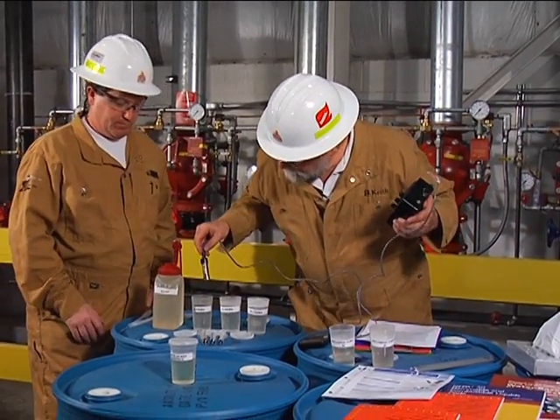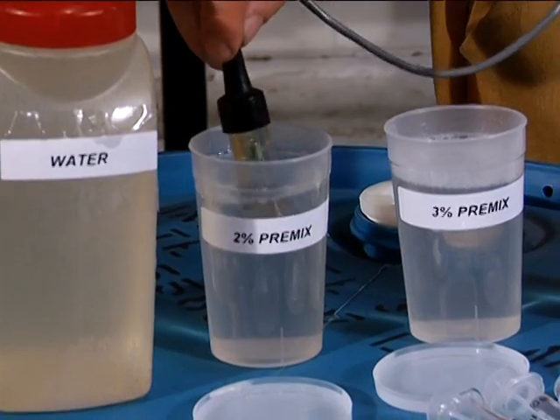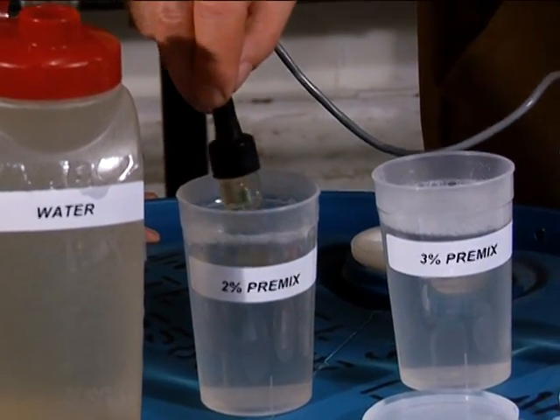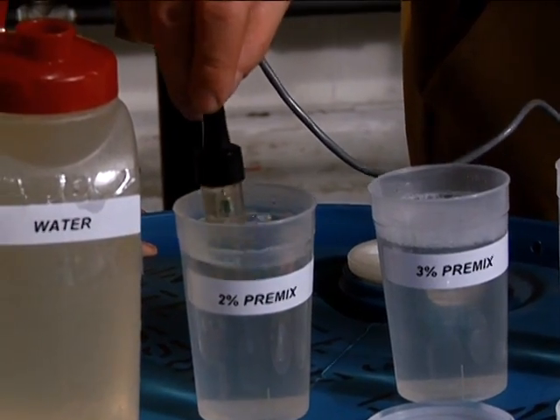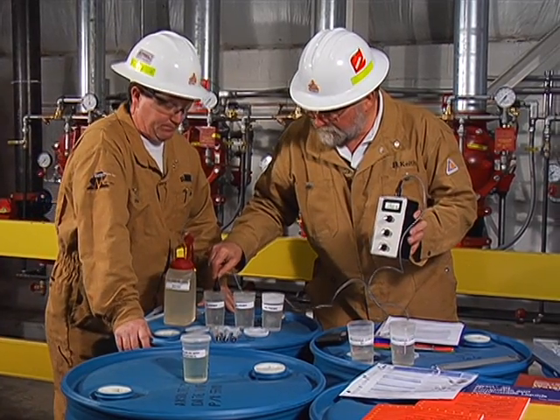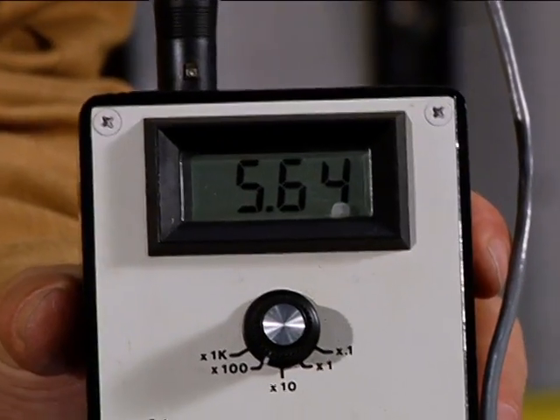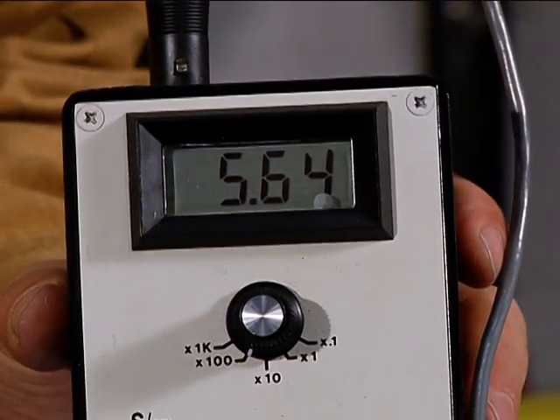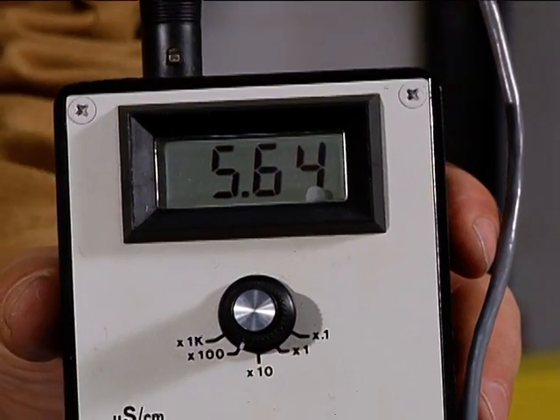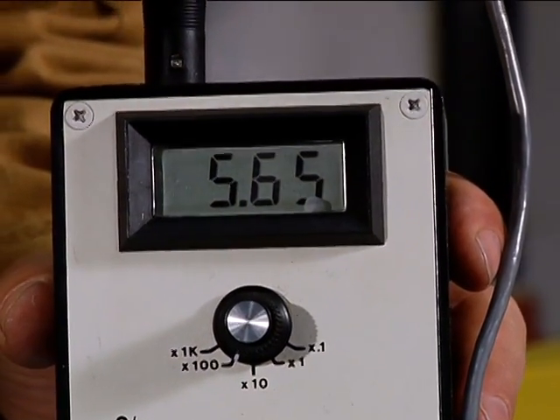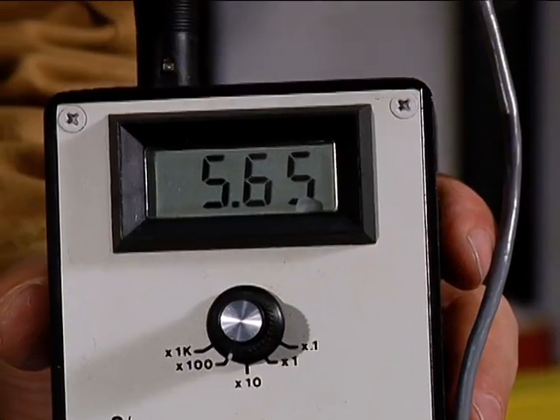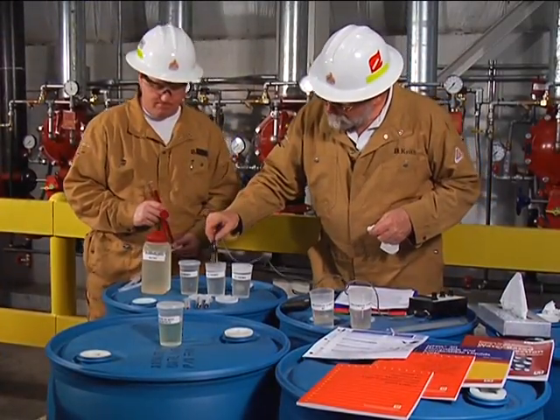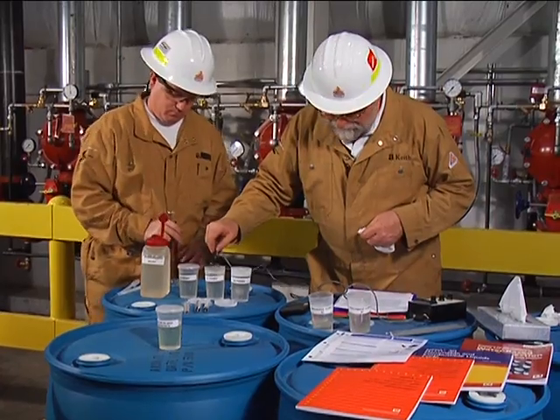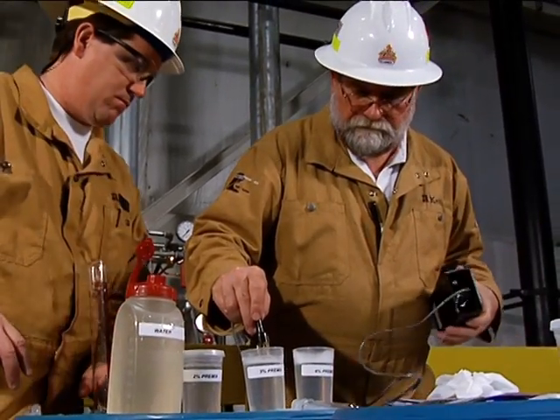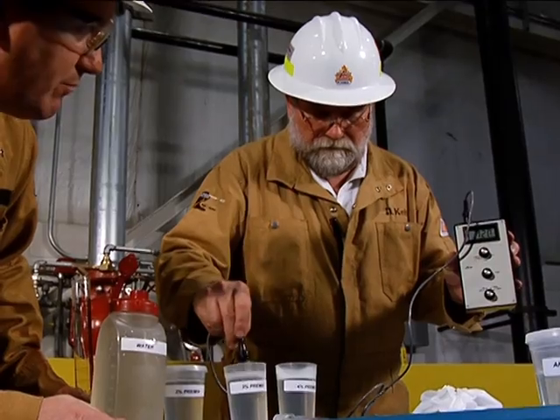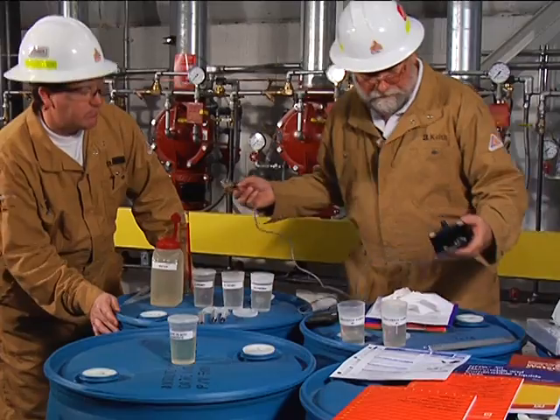We'll first do the 2% premix. And when I'm doing this, I'm also stirring slightly the conductivity probe in the solution. And we'll wait until it stabilizes. Good, 5.65. 5.65? Yep. Okay. Next, our 3% calibration standard. 7.20. 7.20.